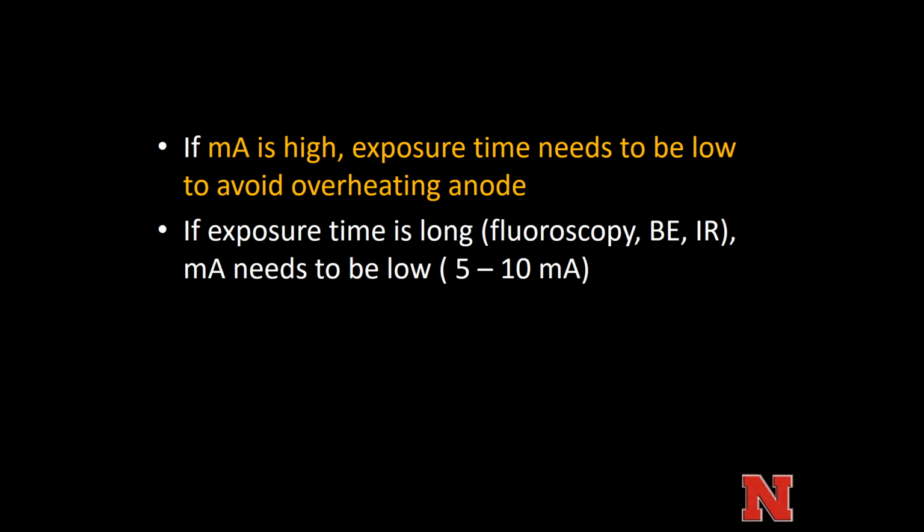You're going to have to change the mA to be on very low because intrinsically you need it to be on for a long time. So what happens in those setups is instead of doing like a 300 milliamp mA with a millisecond exposure time, you're going to have an exposure time in minutes, but you're going to have to drop the mA to keep the overall anode from overheating and also to just reduce the chance of like a skin burn occurring on your patient.